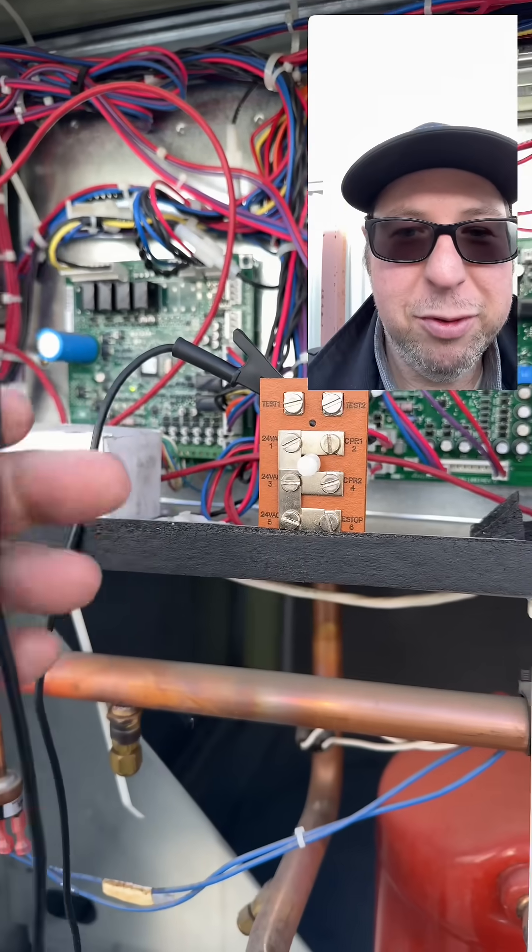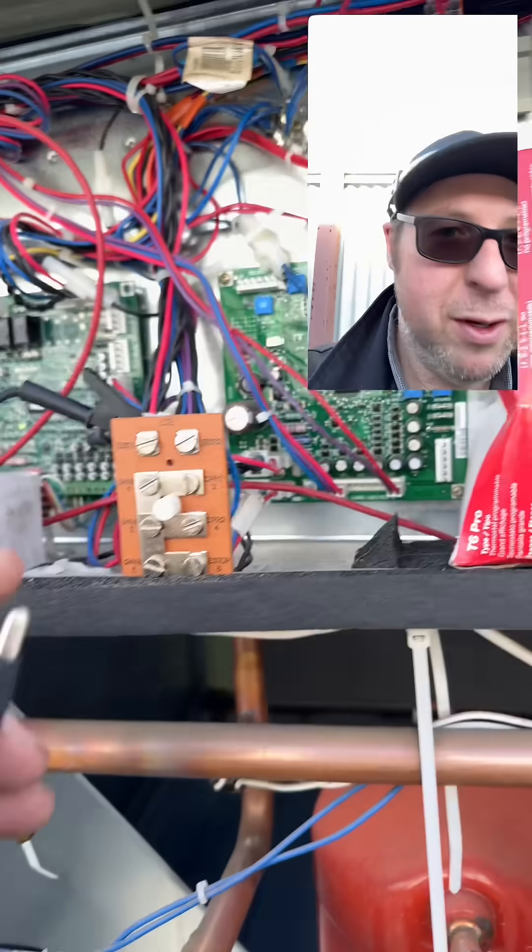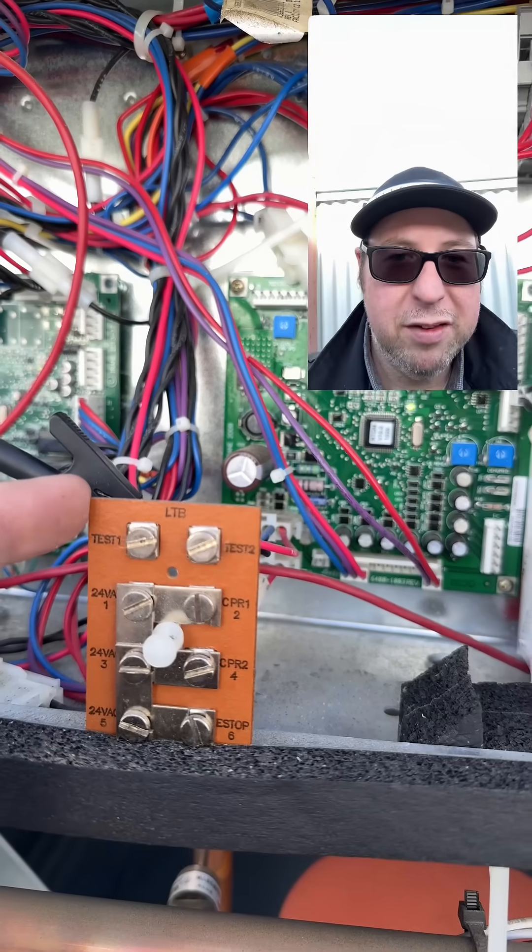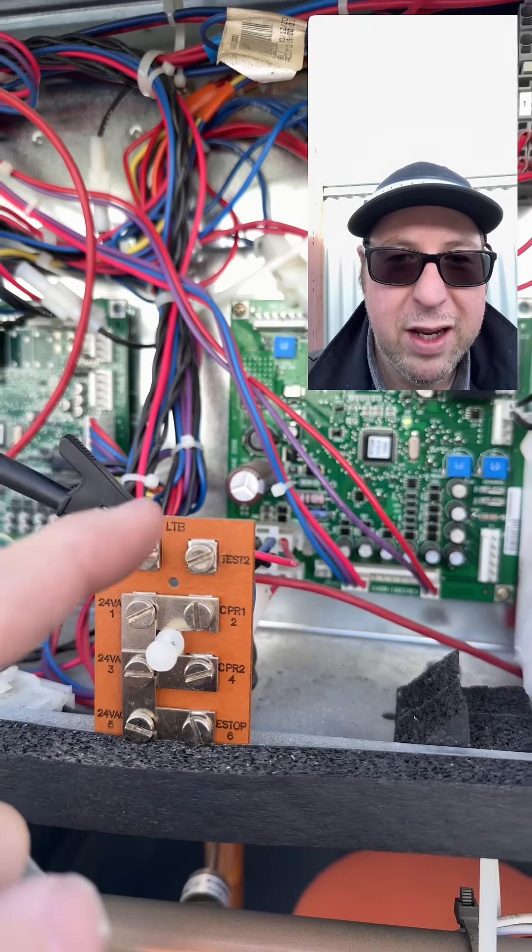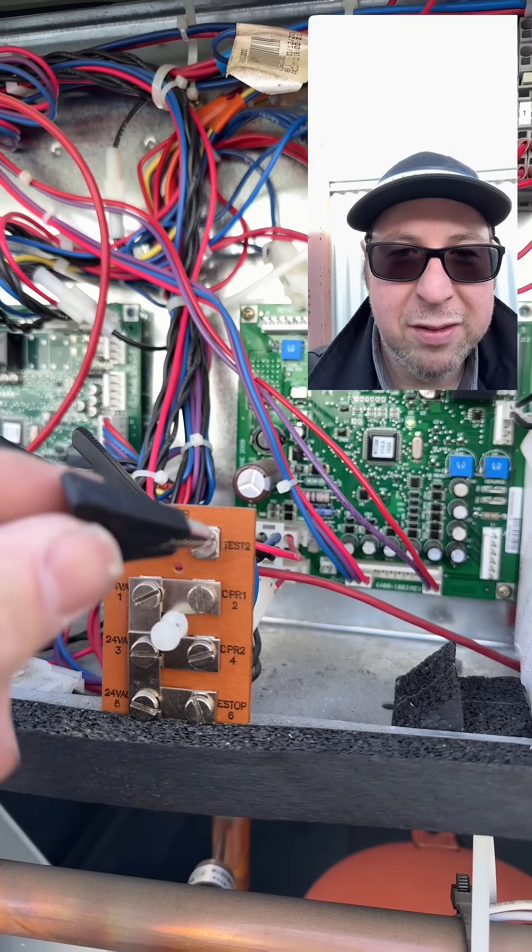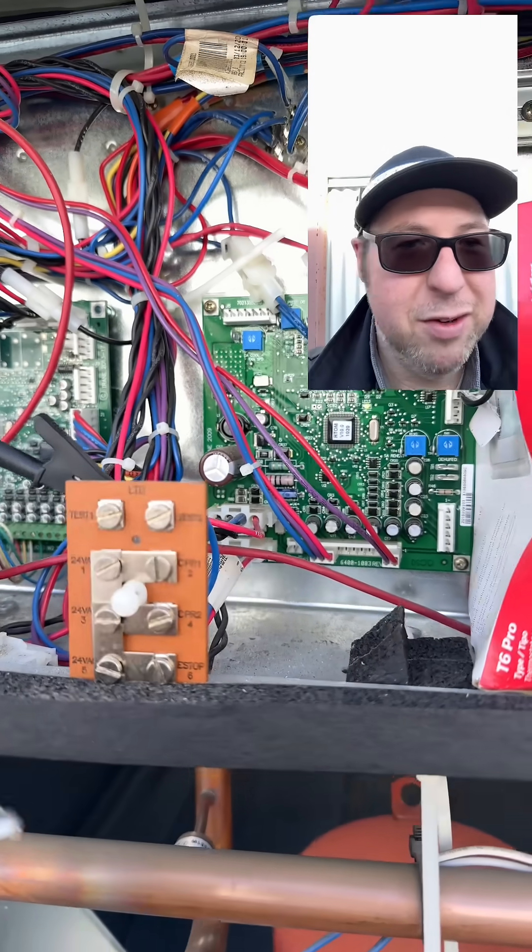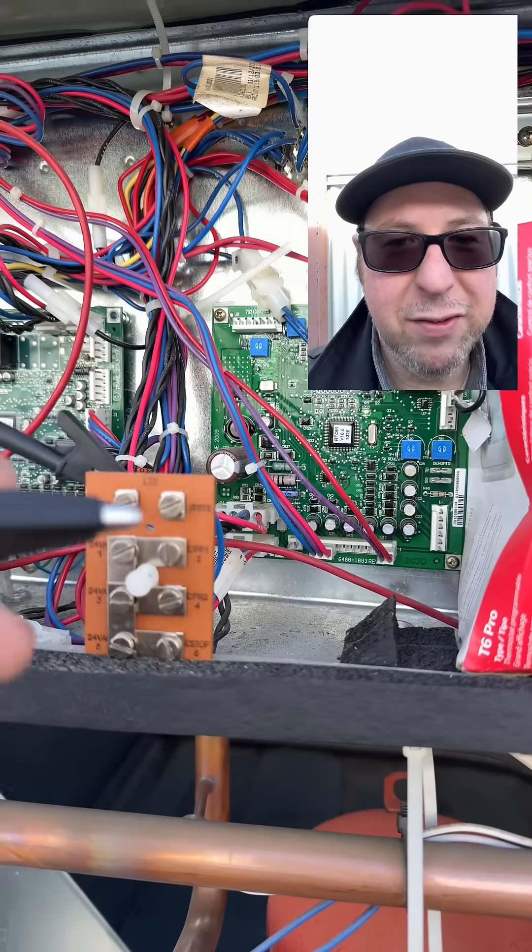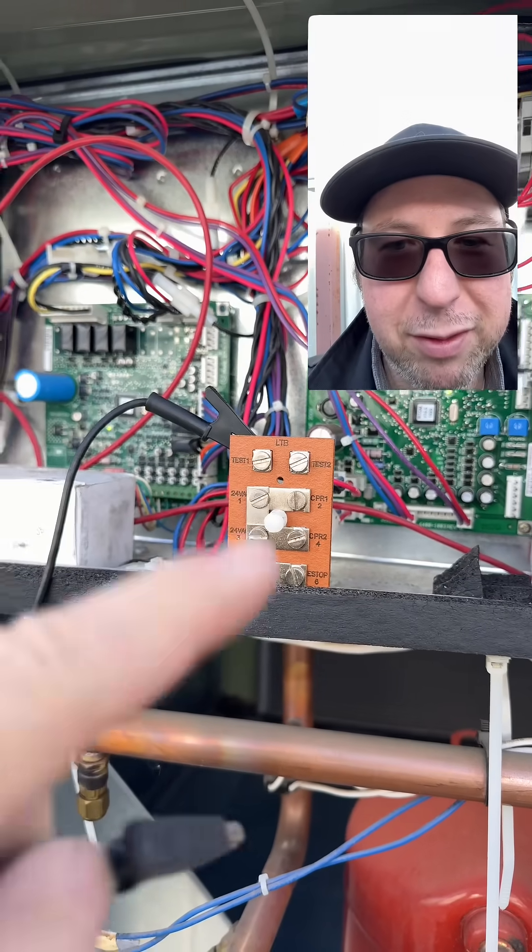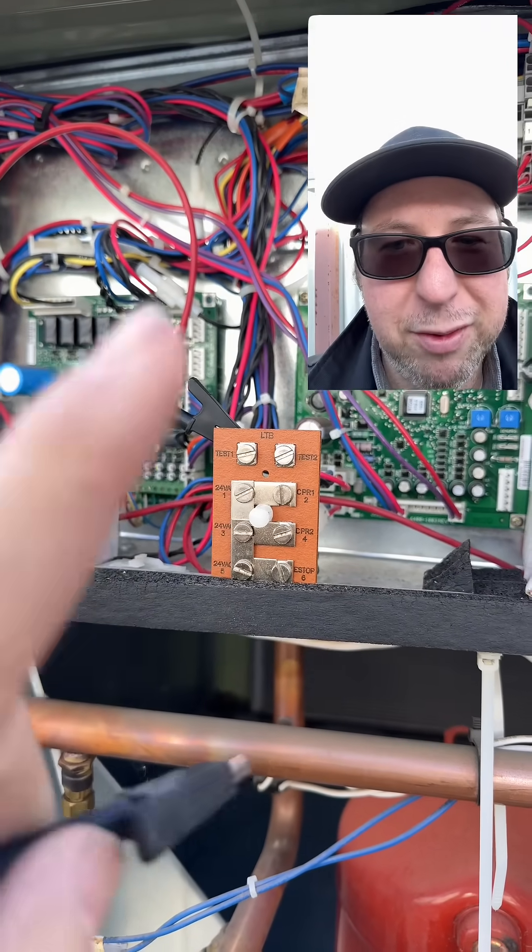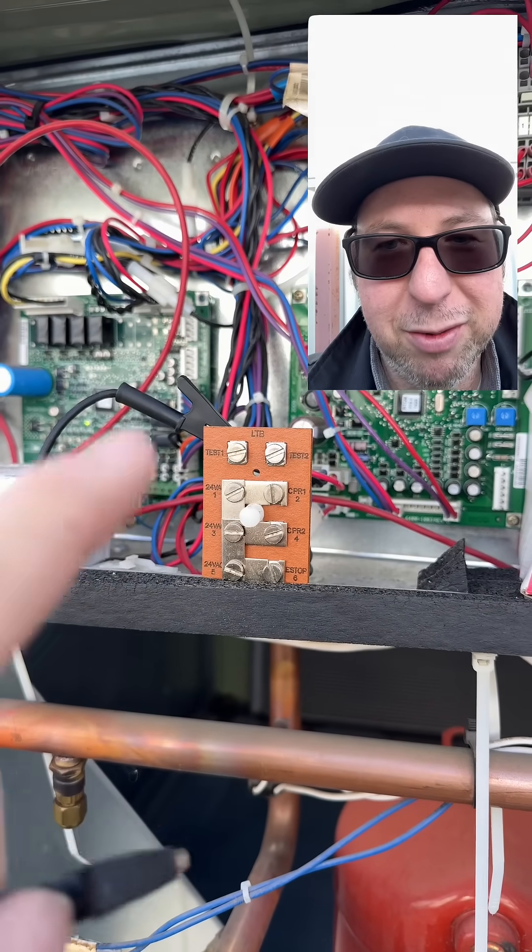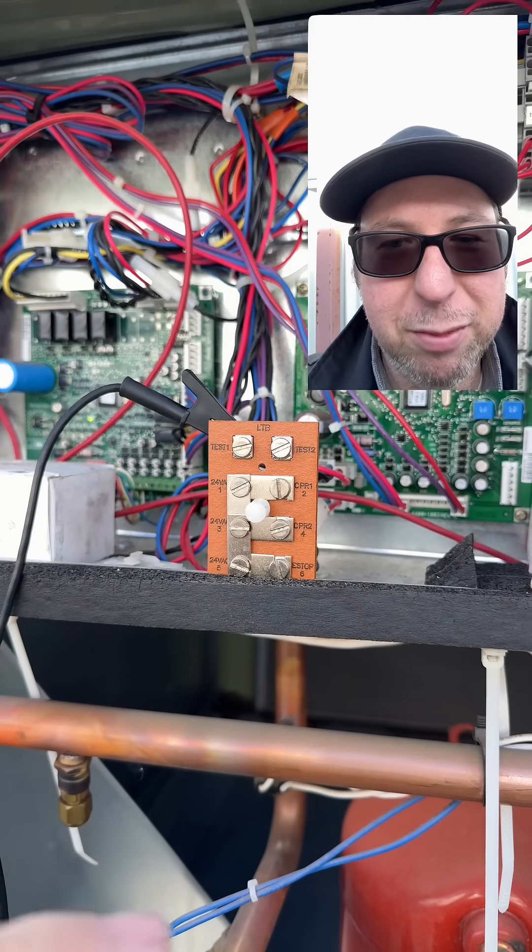What you do is you take your jumper cable, you're going to put one on test one and then you'll put the other one on test two. Now you can just leave it on there and it'll cycle through everything, but it'll do it real quick so it won't get through the entire ignition process for heat.